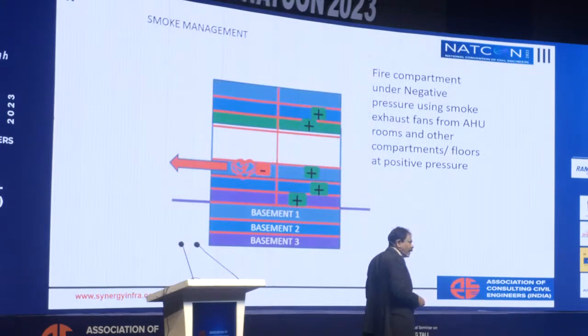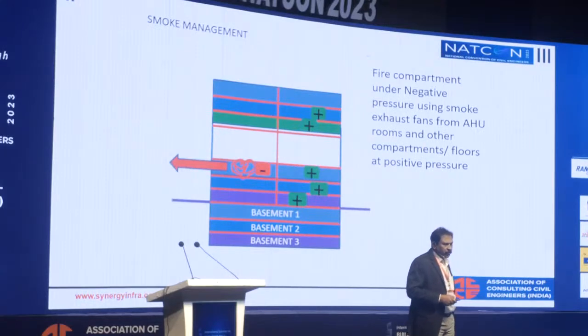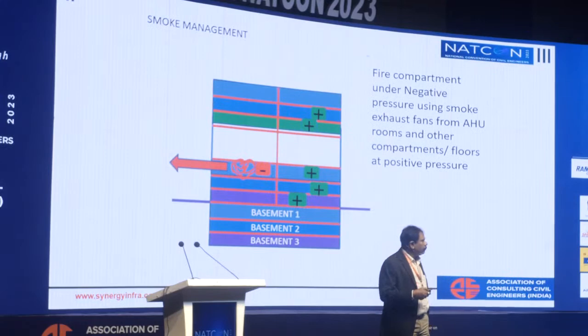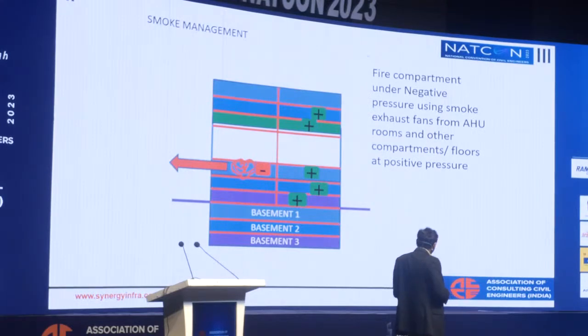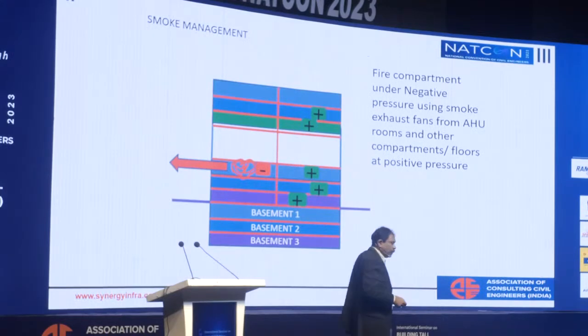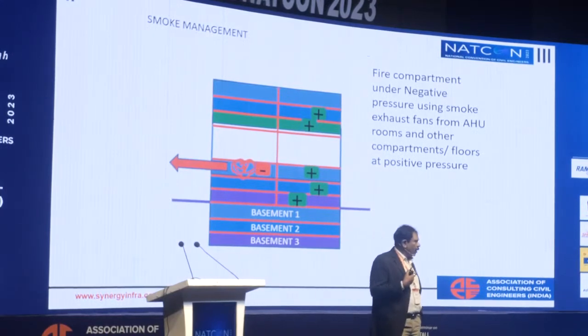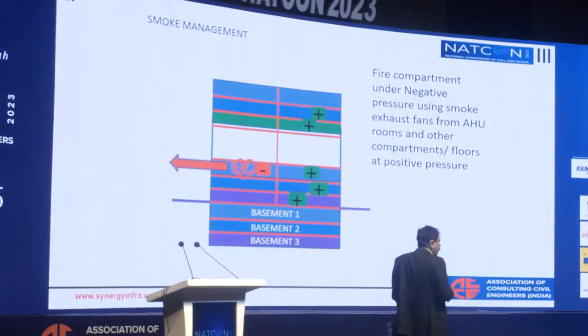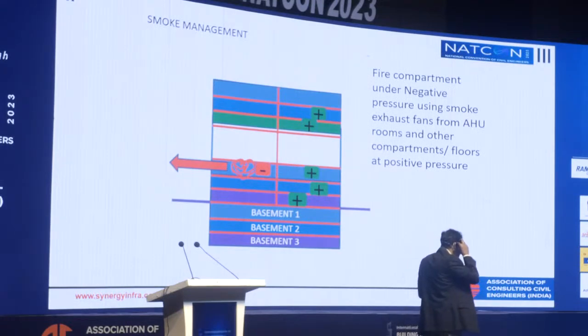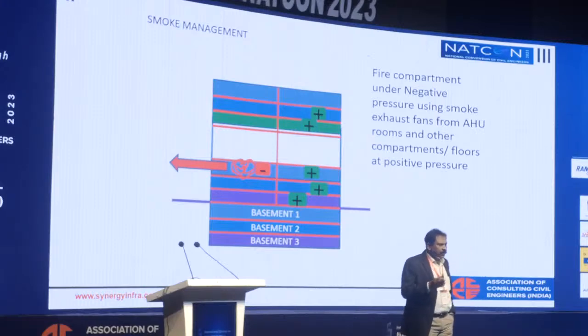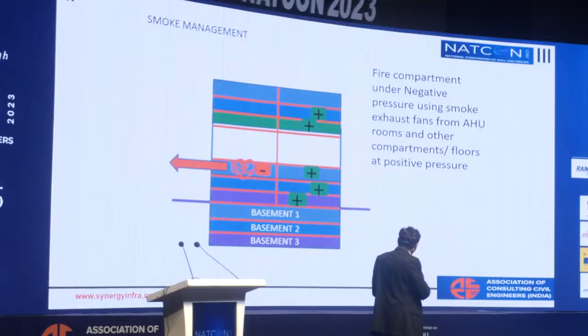And one more thing is smoke management. Even though our code does not specify smoke management, it's only part of the performance-based design, but still some of the projects, some of the MNCs, they insist on this. So what we need to make sure is whenever there is a fire, that particular compartment is kept completely under negative pressure by taking away the air, and all the other compartments have to be under positive pressure. The pressure differential between this floor and the other floors or corridors is also specified when we do the CFD modeling, how much is to be maintained so that the smoke will not enter, depending on the fire loading. And once this is maintained under negative pressure, then the smoke will not spread to the other floors. So this is also one of the most important things when we look at tall buildings.